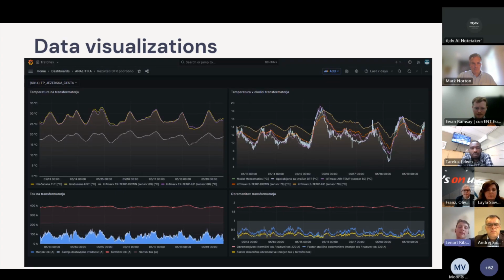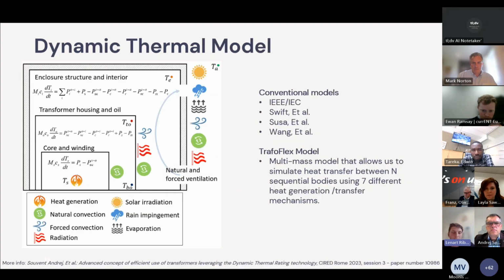And then we also made data visualization using Grafana. Here you can see four graphs, and the most important one is the one on the right in the bottom, which shows the loadability of transformers. The blue and the yellow line show the current loadability, which is around 0.5, which means 50% of the rated power. But the red line shows the possible transformer load, which could be even up to 1.7 times the rated power. This shows promising results for DTR also in our grid. So next, if we proceed, we'll go a bit more into the technical details, and I'll give the floor to Andrej to present it.